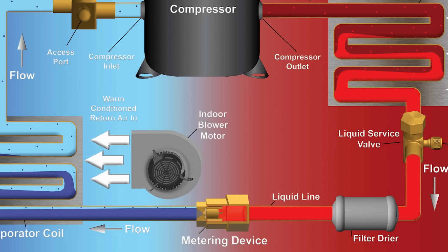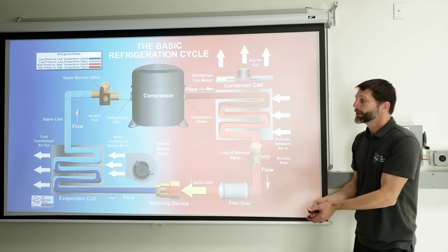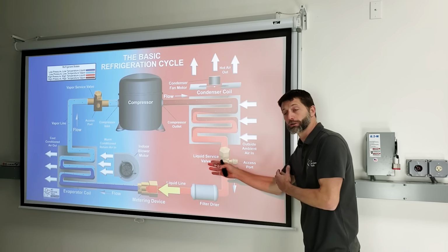But really, as you can see, there's a little bit of light blue at the top. That is your little bit of vapor refrigerant. So what's happening is you're reducing the pressure so much that the refrigerant has a chance to expand. And so you have 80% liquid, 20% flash gas. As the refrigerant enters into the coil, it's already saturated. And saturated means liquid and vapor both exist at the same time. Anytime the refrigerant is saturated, you have a phase change occurring.